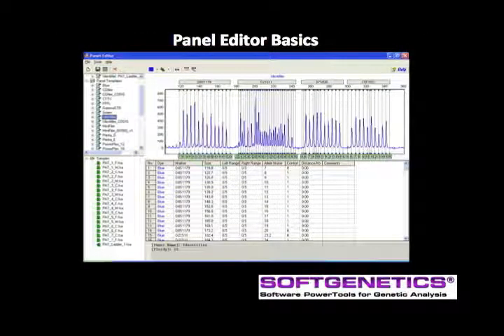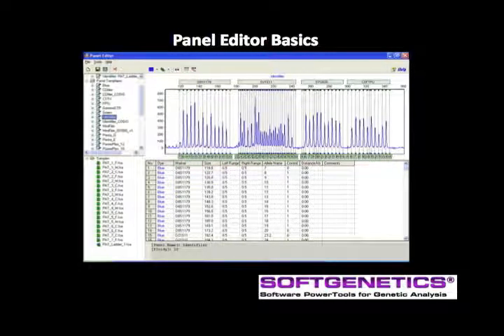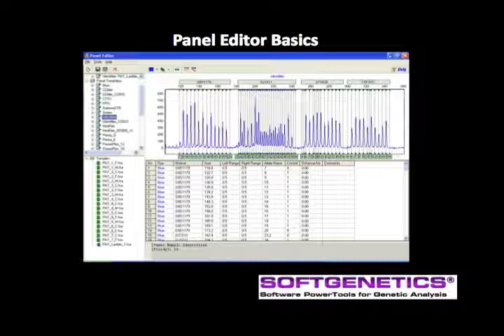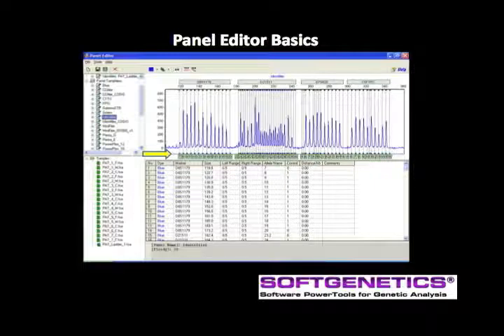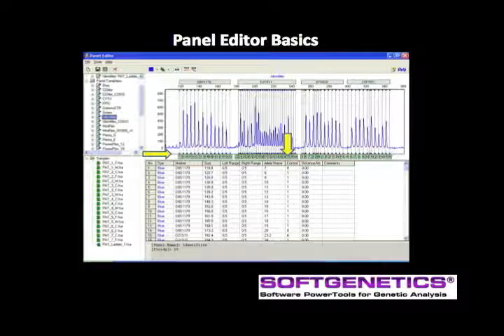Access the panel editor using the Tools drop-down menu and select Panel Editor. Select the panel from the list of panel templates in the upper left. Variant or virtual allele bins are indicated with open rectangles at the base of the electropherogram, and major allele peak bins have a solid fill color rectangle. The program treats any bins with a zero in the control column as variant or virtual alleles when Auto Panel Adjust is selected in the third screen of the Run Wizard.